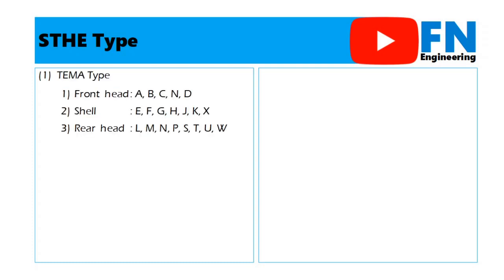The next material is configuration or type of shell and tube heat exchanger. There are four standard types of shell and tube heat exchanger, namely TEMA, HEI Type, ASME UHX Type and Hairpin Type. TEMA Type has three different configurations. There are front head type, shell arrangement and rear head type. The types of the front head are A, B, C, N and D. Then the types of shell are E, F, G, H, J, K and X. Lastly, rear head. There are L, M, N, P, S, T, U and W. For detail, I will explain in the next slide.